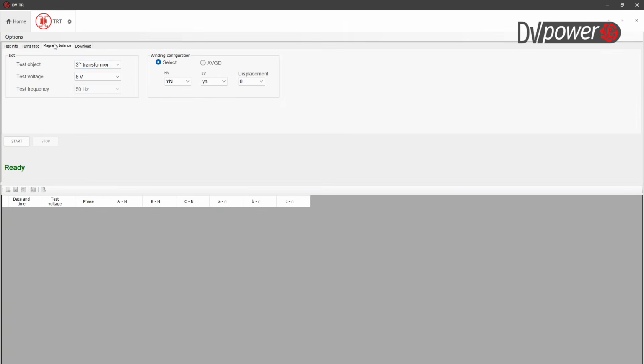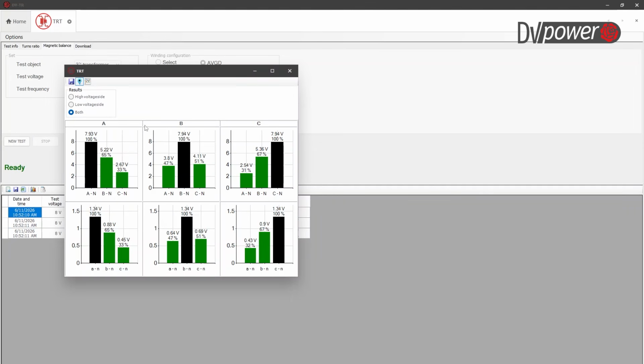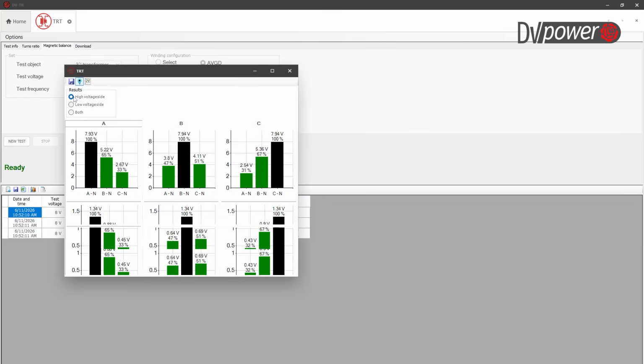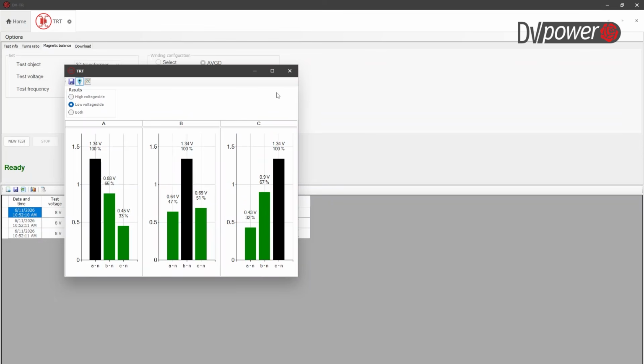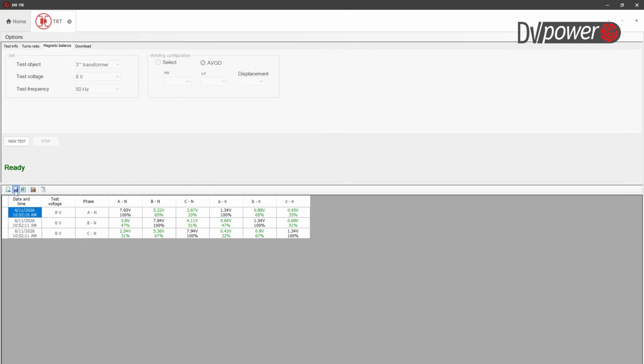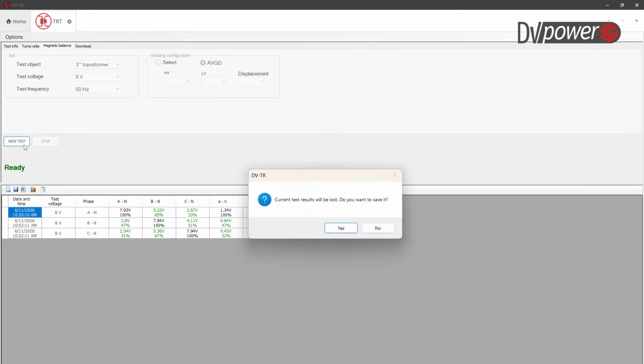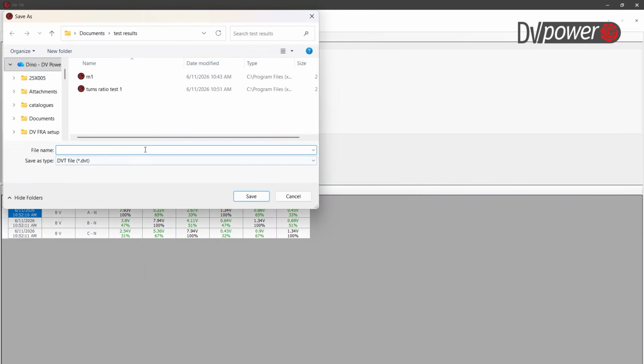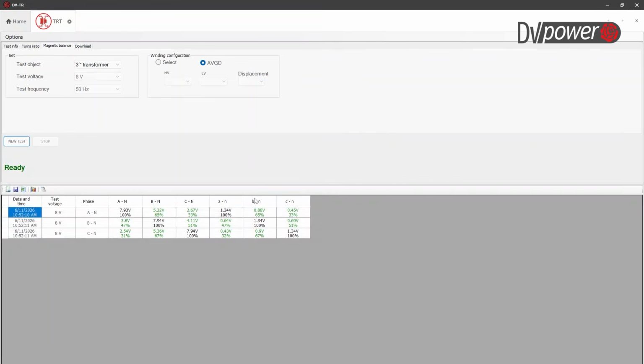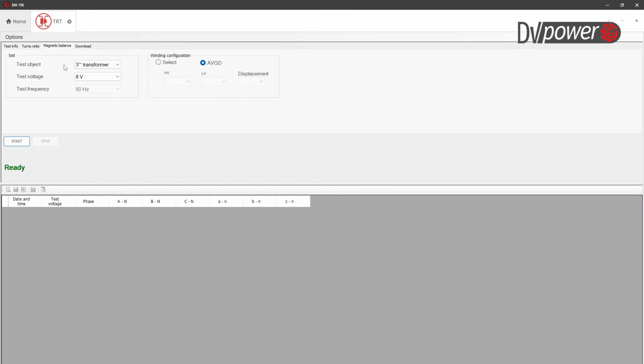We can now perform magnetic balance test. For this test, we use the same setup. We can again automatically detect a vector group, and we can press start button. And we have our results. We can display high voltage side results or low voltage side results. And we can again save these results. If we don't do it, we will be noted by our software. We will save it as magnetic balance test results. And these are functionalities of our DVTR software with TRT 33C device.